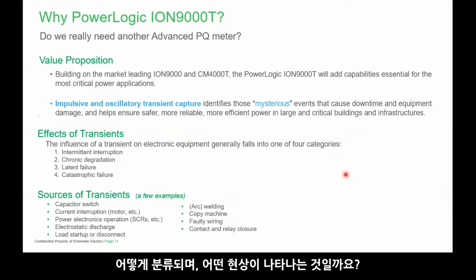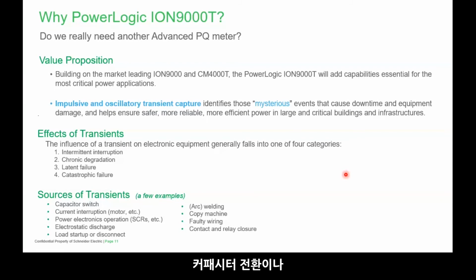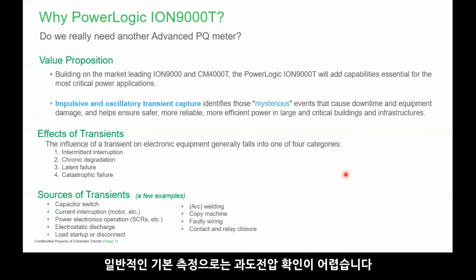And what kind of phenomena will you see transients in? For example, capacitor switching, and also welding, maybe some current interruption, or, for example, motors. There are many different types of transient, and if you want to capture transient, you really need to have a very high resolution sampling rate meter to do this. It's not any conventional basic metering that can capture transient.